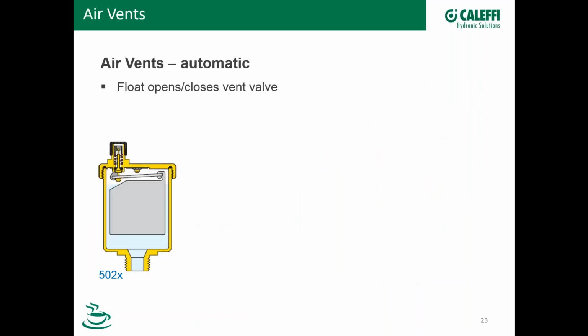Okay, let's talk about an automatic air vent. Here's a cutaway, which is really nice. It shows the float inside, and I don't know if you can see the water level here, but what happens is as air builds up inside of the body of the vent, this air gap on the top increases in size, and so the float will drop, and at some point it's going to drop enough so that this little linkage right here is going to pull down on this needle valve to let the air vent out through the vent cap. So this float just moves up and down to open and close this little tiny needle valve right here and let the air out. That's the fundamental function of an automatic float type air vent.